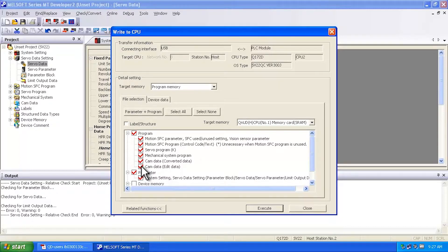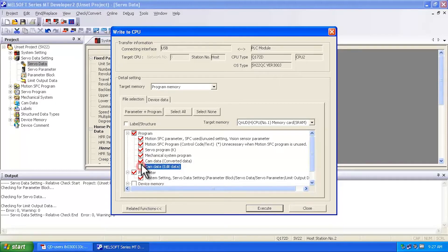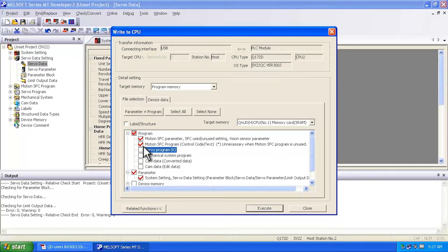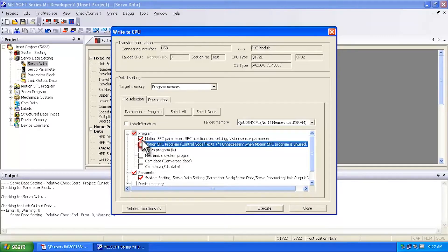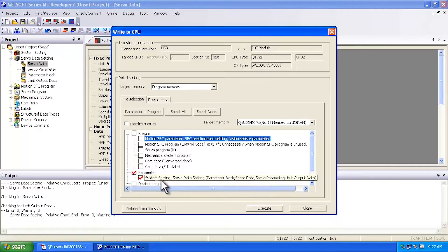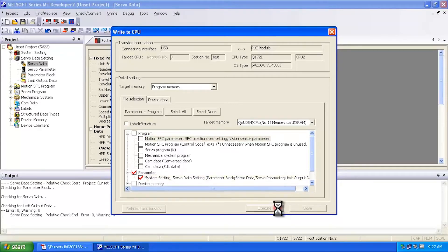So uncheck that and then make sure you uncheck a bunch of this data that you're not downloading. Otherwise, you'll get error messages and it gets confusing. So uncheck cam data, uncheck mechanical system data, servo program. All you're concerned about right now are the system settings to clear the system setting error. So we're just going to write that.